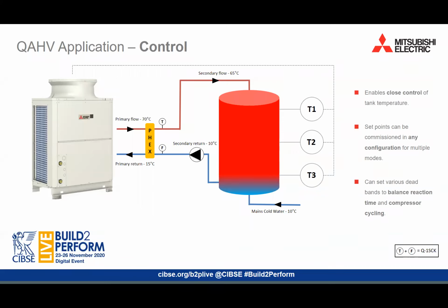The QAHV controls the temperature in the vessel via 3 temperature sensors located in sensor pockets at the middle, top, and bottom of the vessel, shown here by T1, T2, and T3. The unit can then be commissioned to control the vessel temperature according to the target set point at any of these 3 positions. So for example, let's say we're targeting a set point of 65 degrees Celsius.